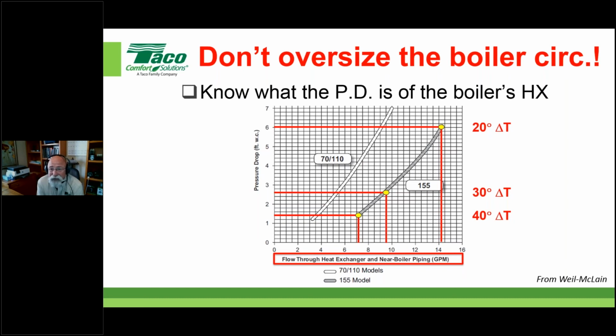It is. And that's why the boiler manufacturers are finally putting this information in their manuals, because they get it too. Here's the thing, I'm sticking up for these guys because I used to work for one, right? When they sell you a packaged boiler, and they put a pump in there, that pump most likely is oversized.